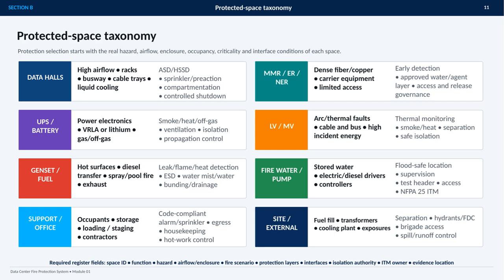The key administrative tool is the required space register. It should capture the space function, hazard, fire scenario, protection layers, interfaces, isolation authority, inspection and testing owner, and evidence location. That register connects design intent to ongoing governance and maintenance.